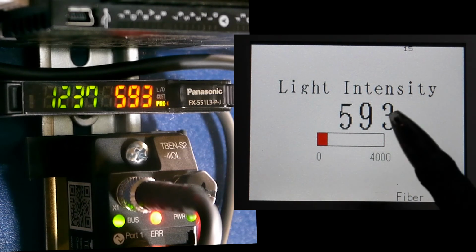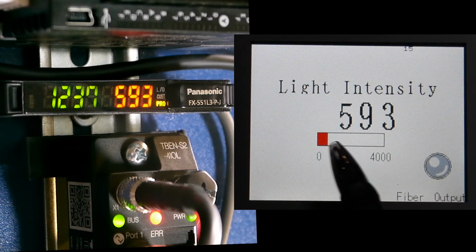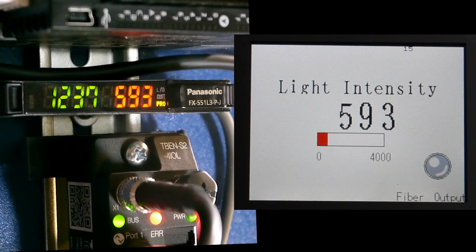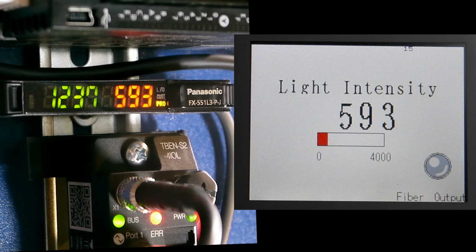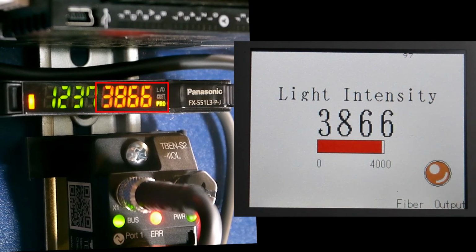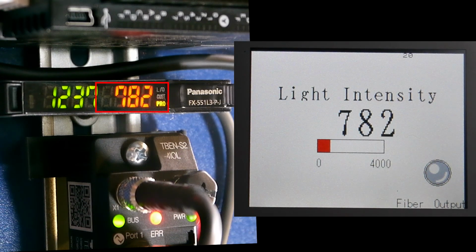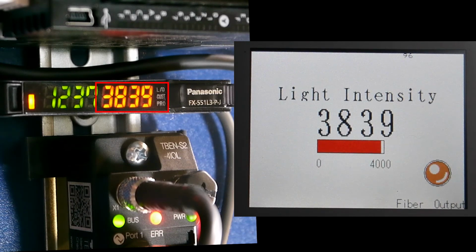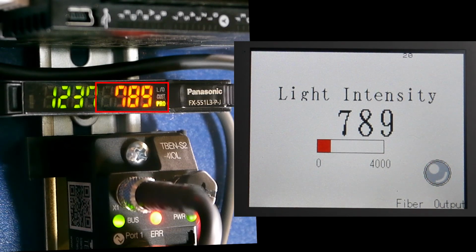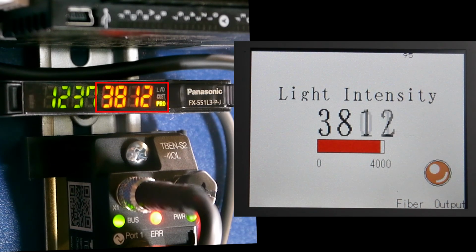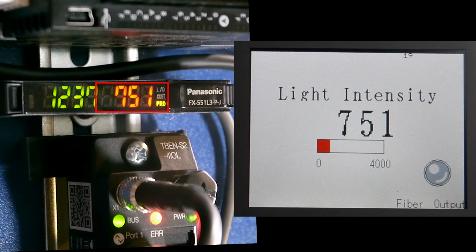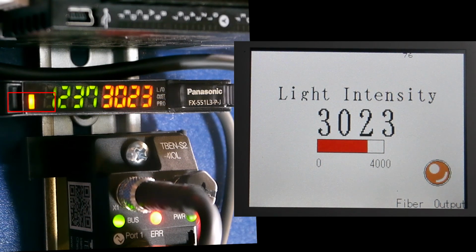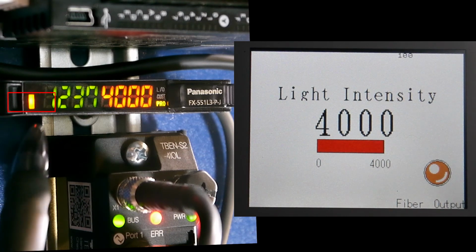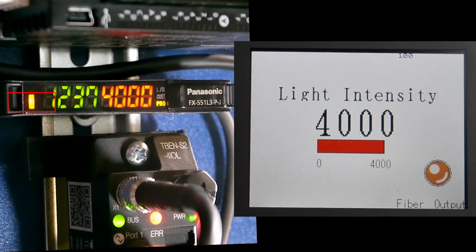So right here, we have the incident light level. I put together a little simple bar graph to also show that. And this right here is the real world fiber optic output. So as I move a part in front of the sensor, you can see the incident light level changing. And you can see that it matches the incident light level on the fiber optic amplifier. You can also see the output light on the fiber optic amplifier and the output light on the display.